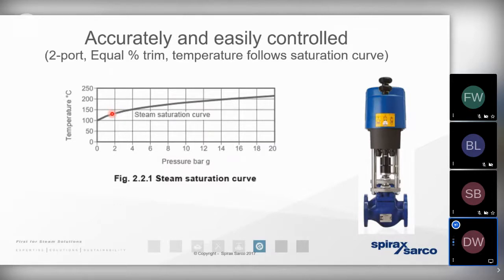The second benefit is we know that when steam condenses, it gives up its latent heat energy. There's a change of state. There's an exchange of energy, but there isn't an exchange of temperature. So the steam that's being distributed at 10 bar gauge, the condensate that exists as a result of that heat loss, is going to exist at 10 bar gauge, 184 degrees.